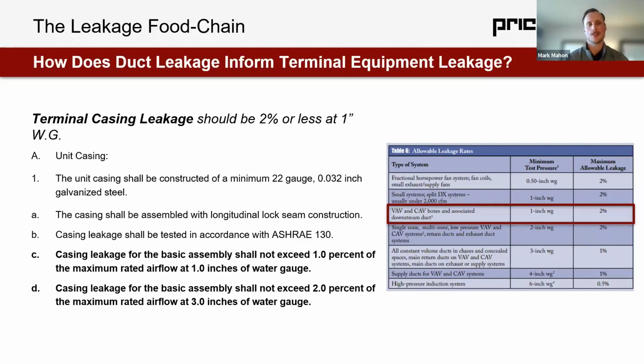When we look towards a higher pressure, casing leakage should not exceed 2% of max rated airflow at 3 inches. So increasing the pressure threefold, only resulting in 1% extra leakage. This is where those specification recommendations or specification notes from manufacturers come from.